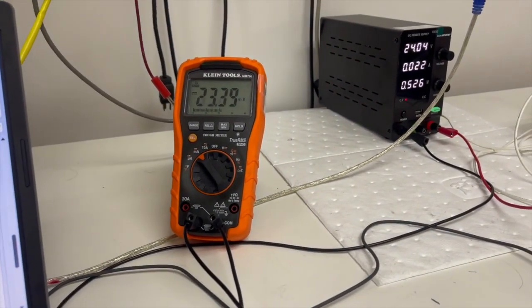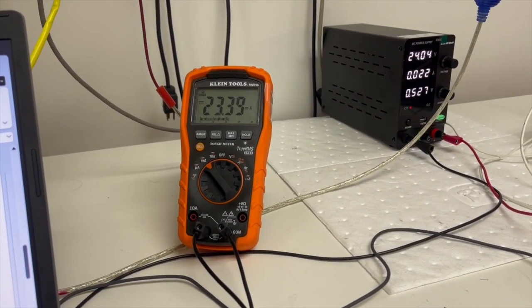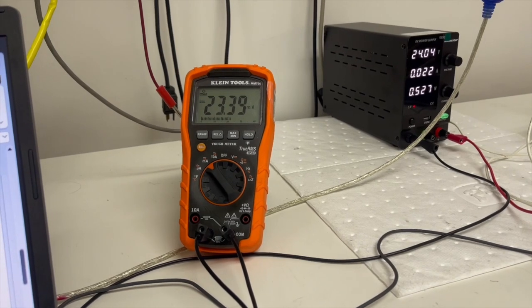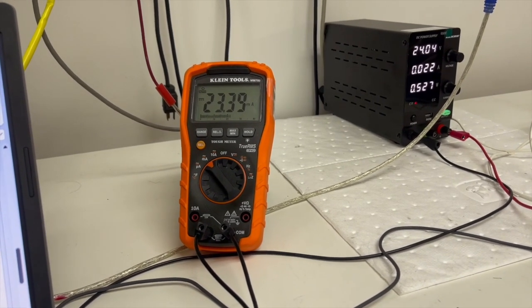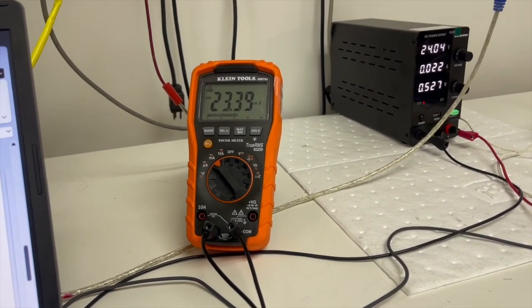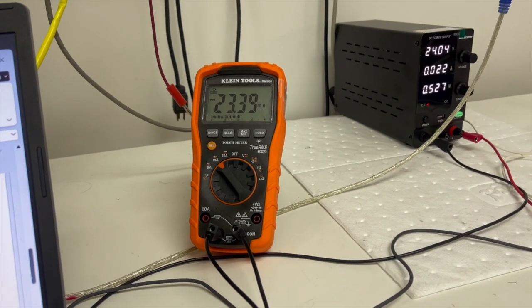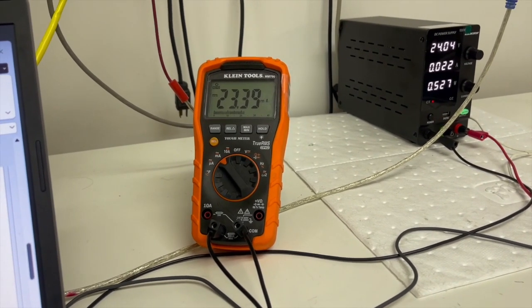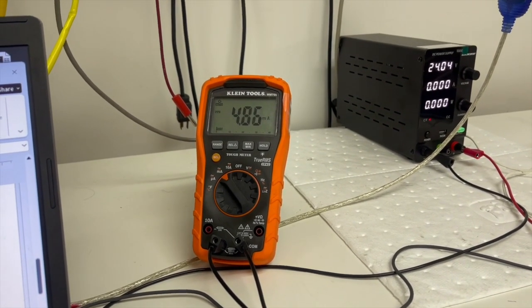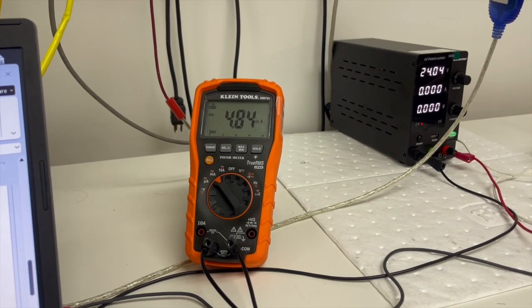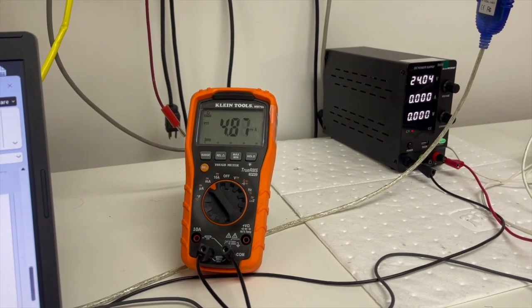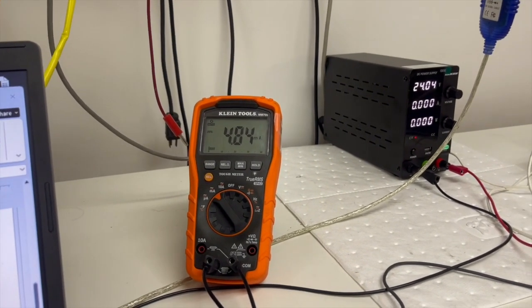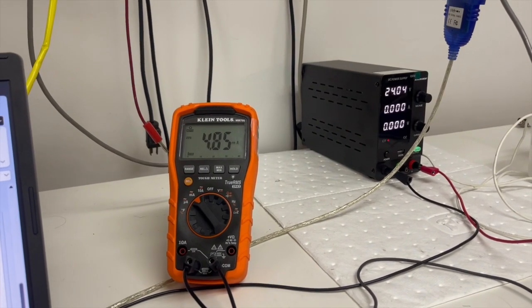Turn it back on, and just verify that it goes full scale like that, 23.39, and then drops back down to about 4 point something. 4.84, so that's working properly. Now we can move on to calibrate the temperature loop.